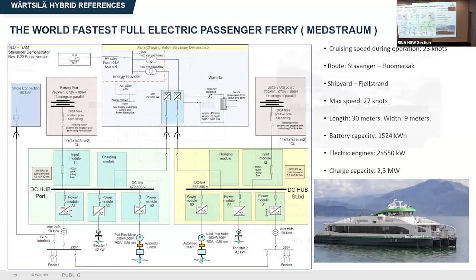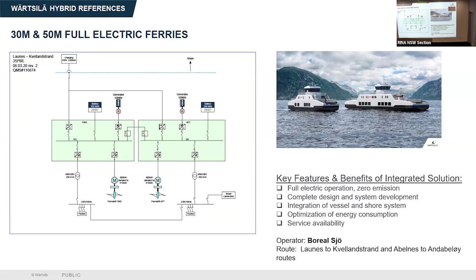Another reference is again from Norway, where the operator of these two boats is Boreal, on the routes Launes to Kvellandstrand and Abelnes to Andabeløy. Here we have 2 ferries, 30 meters and 50 meters, with two battery packs and 1 emergency generator of 500 kilowatts, a DC hub, inverters, and motors driving the propellers.